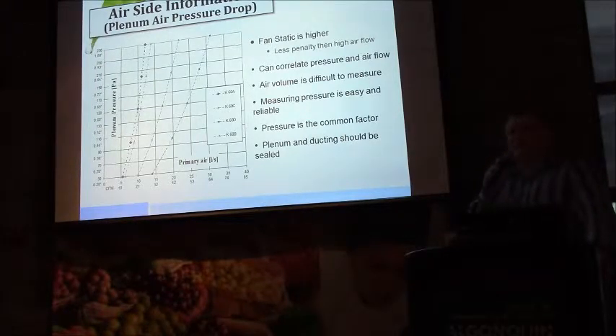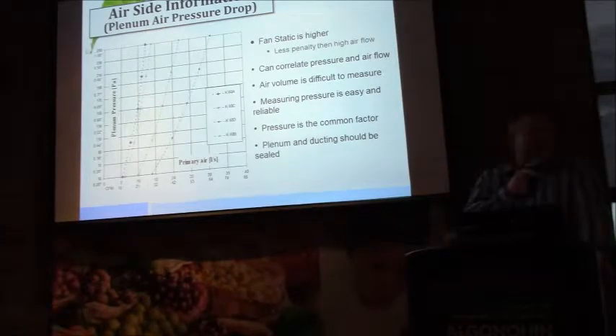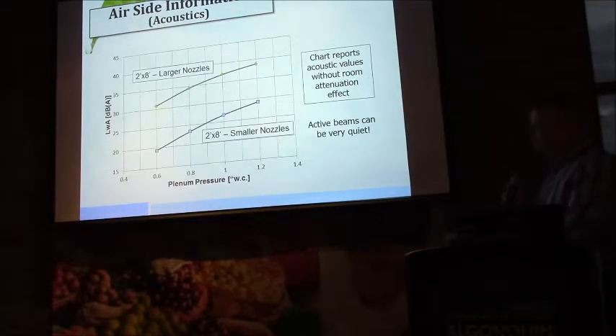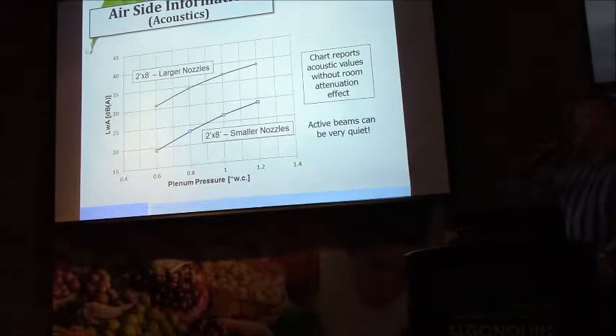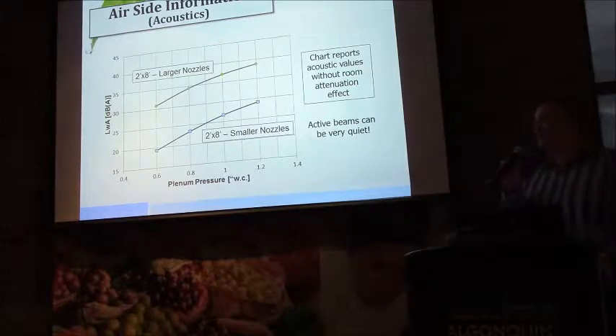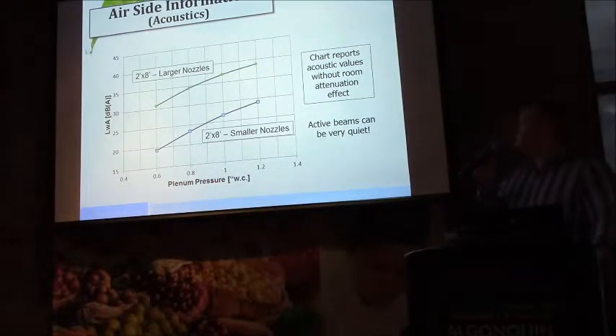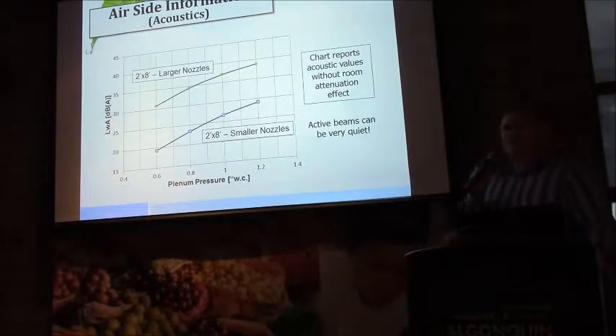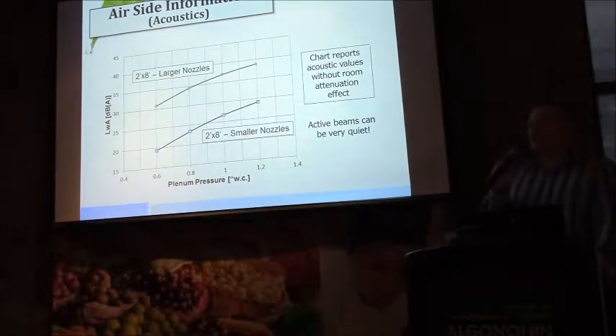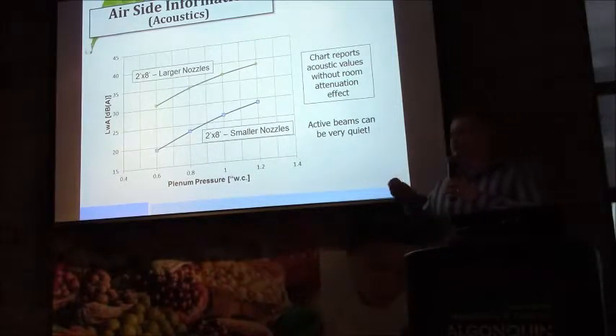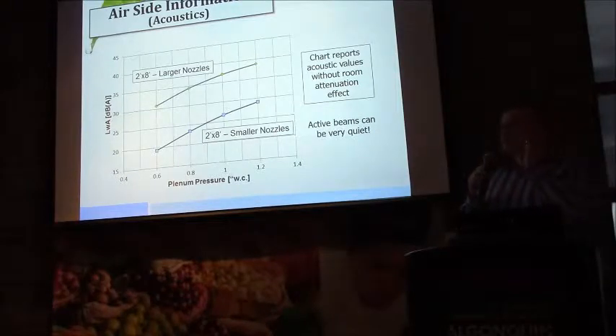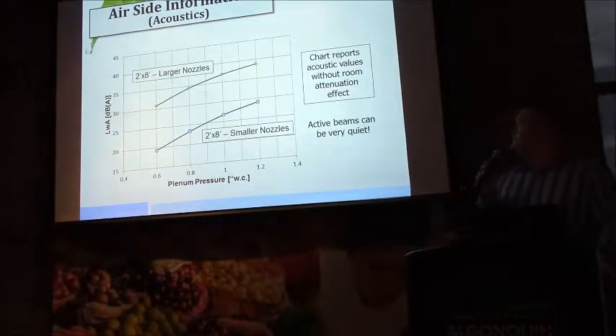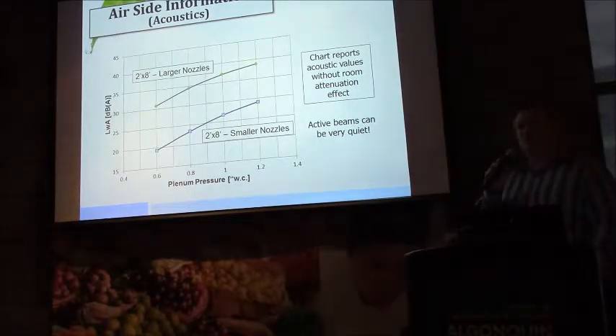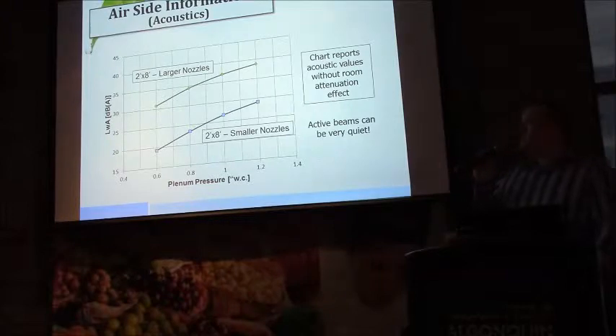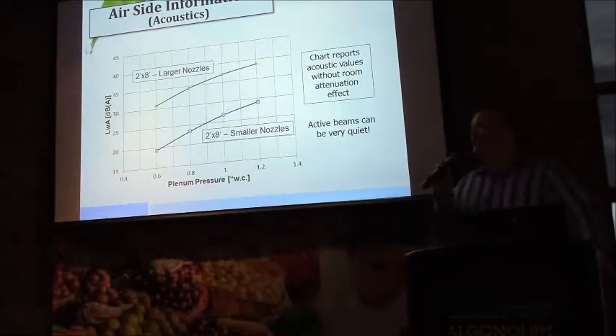And so flow-generated noise becomes a talking point relative to high pressure changes between the distribution duct and the beams themselves. The velocity at the nozzle is in the neighborhood of 6,000 to 7,000 feet per minute, which is a brisk pace in most air discussions. However, the nozzles are very small, and generally the industry has gravitated towards a bell mouth shaped nozzle profile. And so that smooth transition between the static pressure that exists in the plenum and the cohesive jet, which is the goal of the nozzle design, is a more gradual transition. So there's less turbulence and lower opportunity for noise, given that each of those sound sources is also very tiny, even though they add logarithmically.